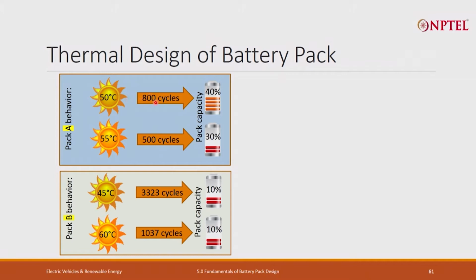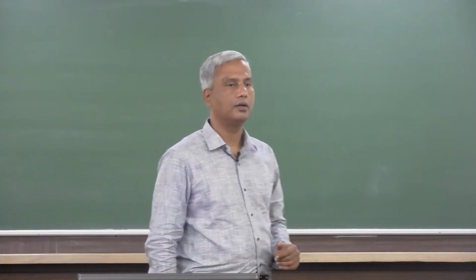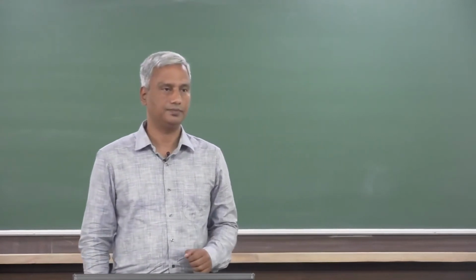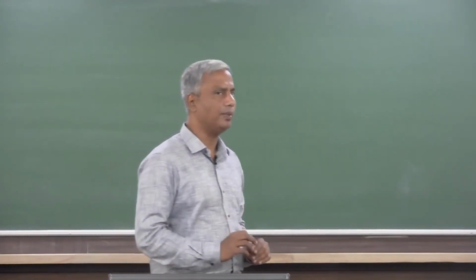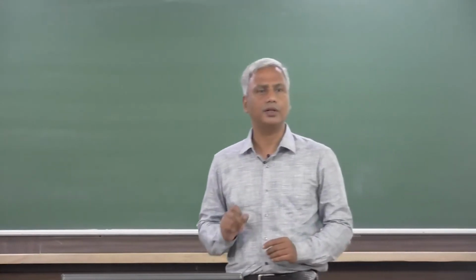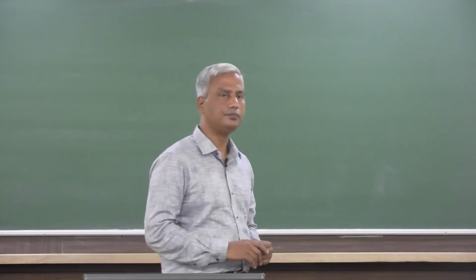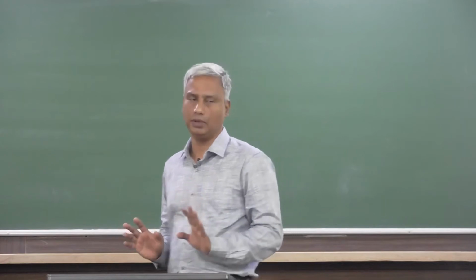In the first case, for 800 cycles, 40% capacity; for 500 cycles, 30% capacity, but the temperature is 50 to 55 degrees centigrade. In the second case, at 45 degree centigrade ambient condition, cycle life is 3323, but the remaining pack capacity is only 10%. The same pack at 60 degree centigrade gives only 1037 cycles. So a change of 15 degree in ambient condition has brought down the number of cycles to less than one-third, keeping the same capacity. However, in EV application, as soon as pack capacity goes below 70%, 75%, or 80%, depending on OEM to OEM, we say this pack is no more usable for EV application.